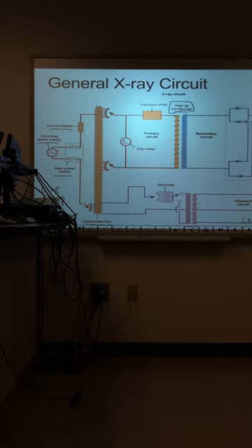Is the step-up transformer considered secondary? So remember, part of it is in the primary and part of it is in the secondary. The primary is in voltage, and the secondary circuit, the step-up transformer, is in kilovoltage.